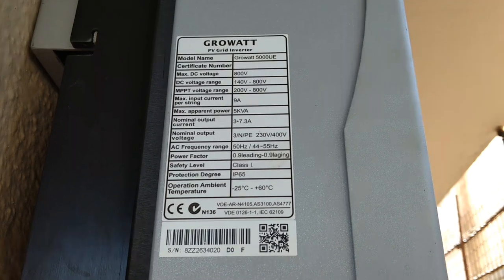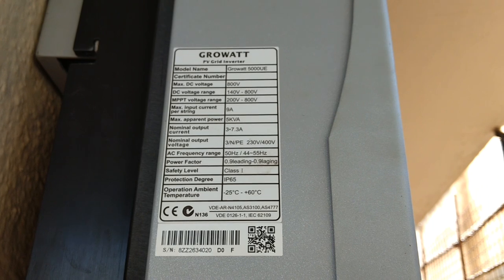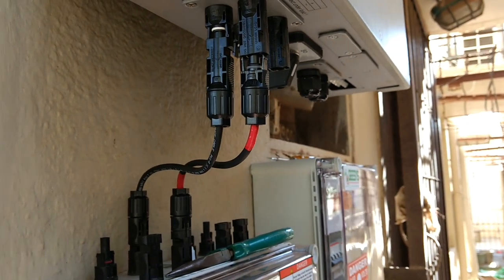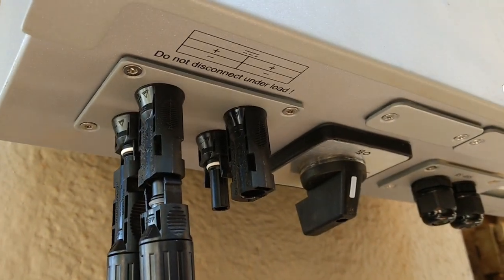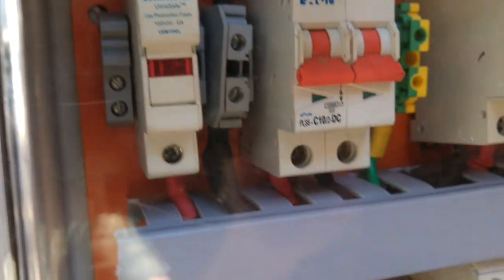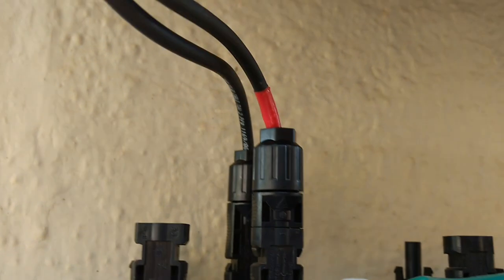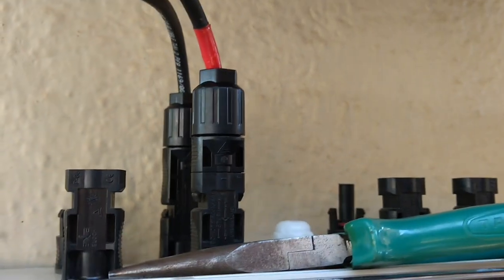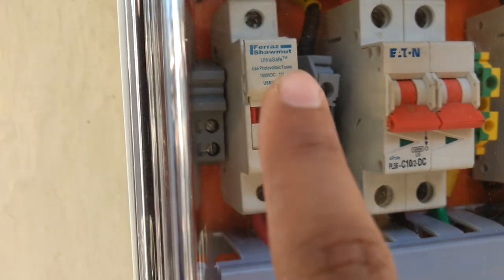Here is the inverter mounted — you can pause the video to look at the specifications. It is a Growatt inverter and the model number and other technical electrical specifications are given. From here we have connected that single array to this inverter, to one of the MPPT inputs — that is 16 panels connected in series. This is the DC box consisting of the DC fuse. The output port is connected with the inverter and you can see the positive is labeled with red tape so there is no chance of confusion.